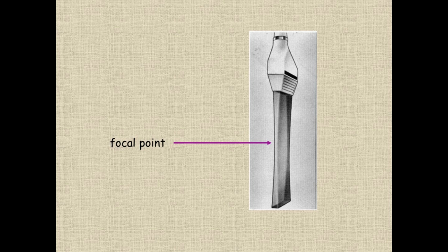The narrower the beam width, the better is the horizontal resolution. We can influence this by adjusting the focal point to coincide with the depth of the structures we're interrogating. Many modern ultrasound machines have one or more focus points that can be adjusted as little arrows on the side of the depth scale and can markedly improve the image quality when manipulated to coincide with the depth of the nerve to be examined.